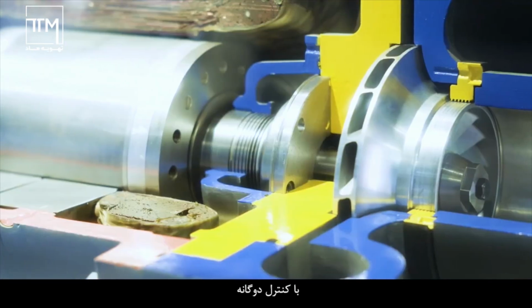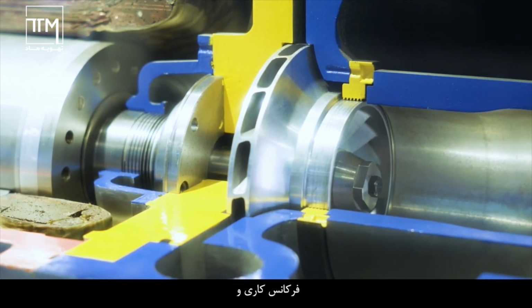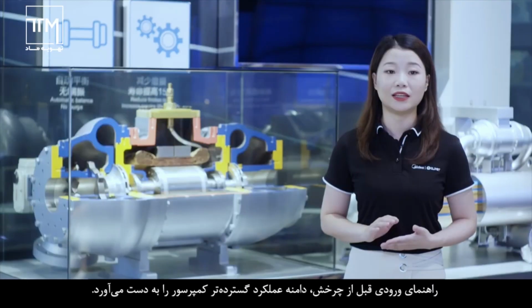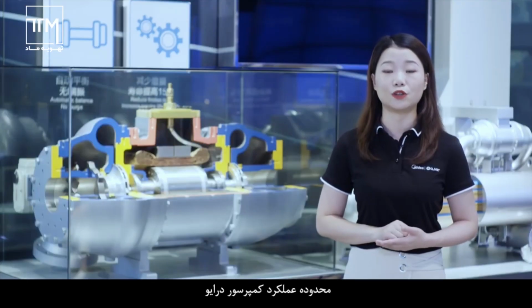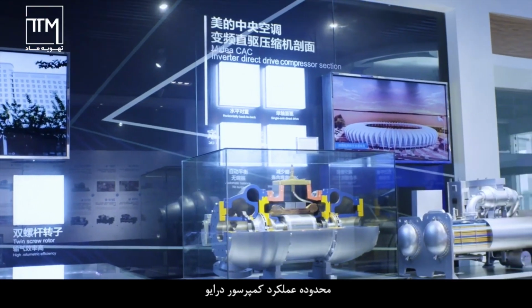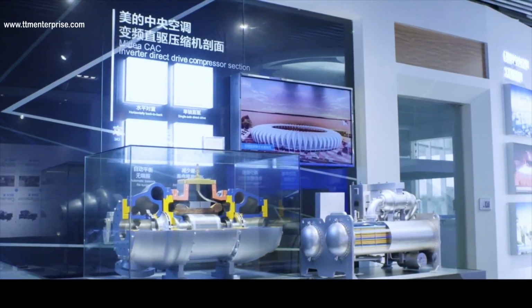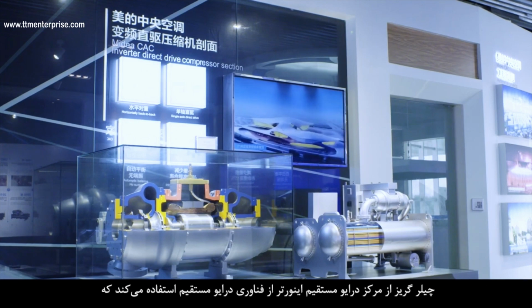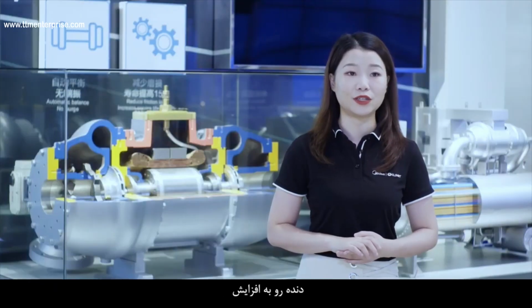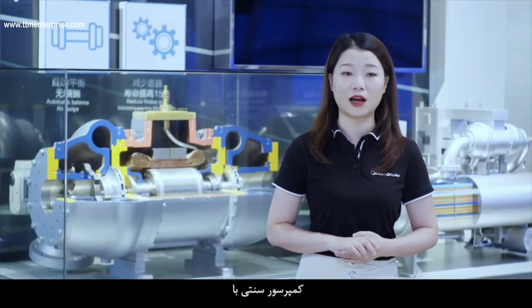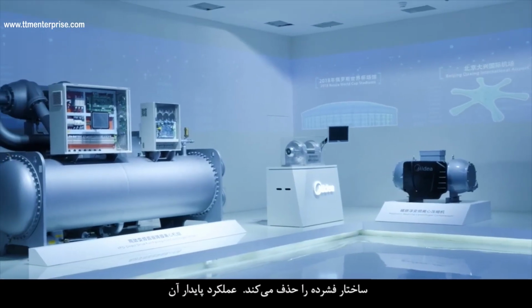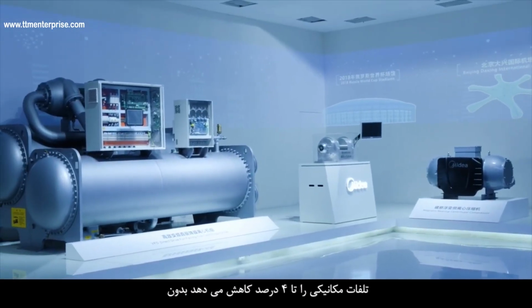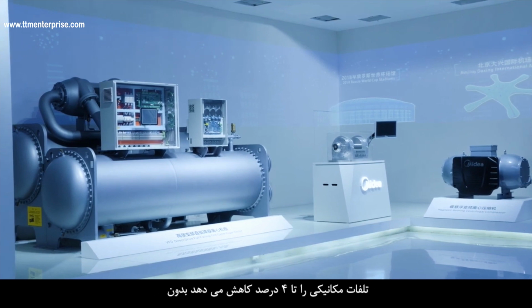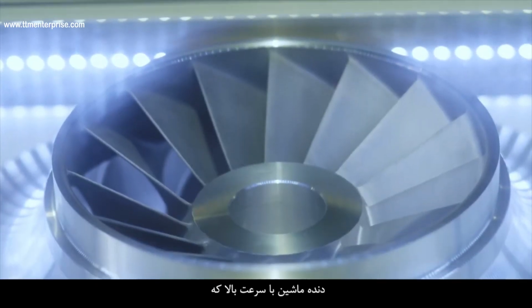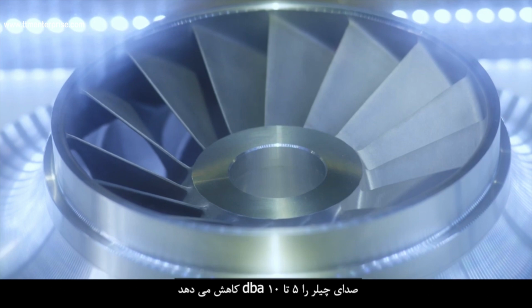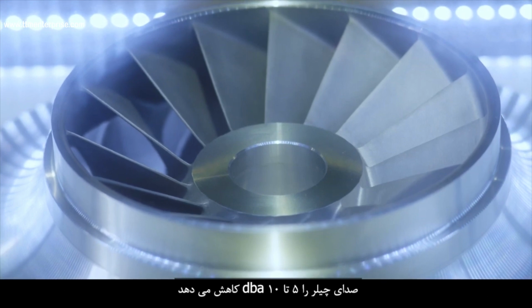With the dual control of operating frequency and the pre-rotation inlet guide vane, it achieves a wider operating range of the compressor. The inverter direct drive centrifugal chiller adopts direct drive technology, eliminating the increasing gear of traditional compressor. With a compact structure and stable operation, it reduces mechanical loss by 4%. No gear high-speed motion, which reduces the noise of chiller 5 to 10 dBA.